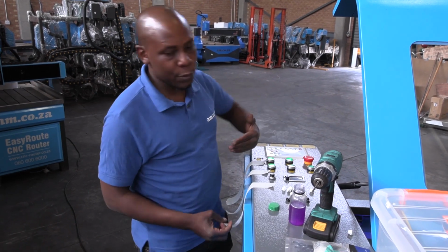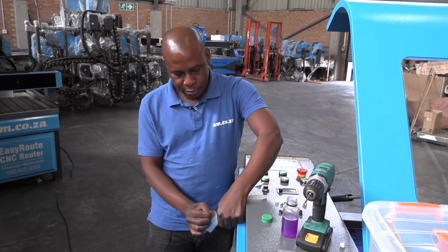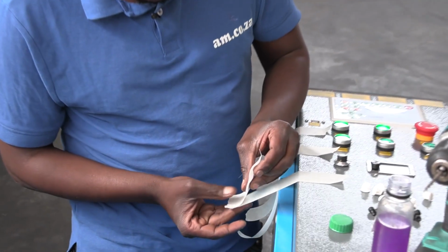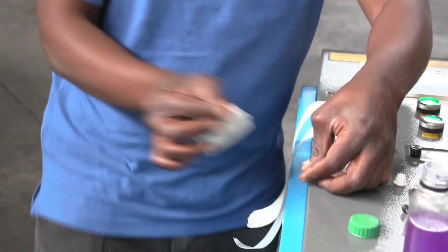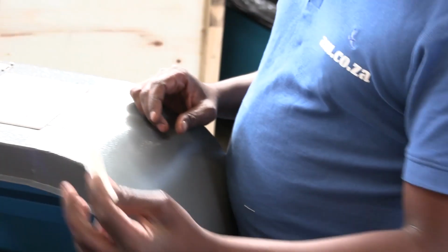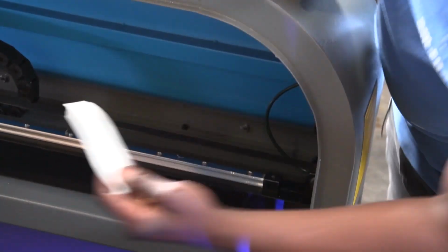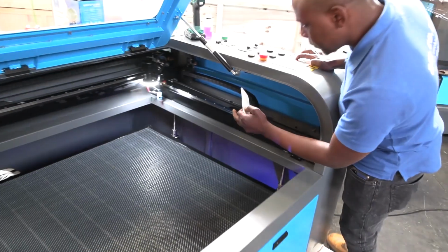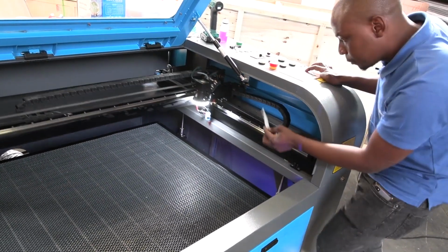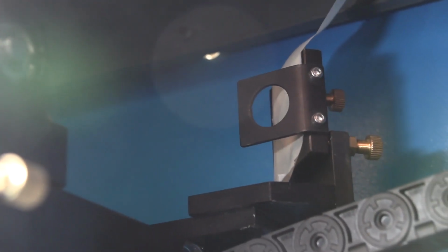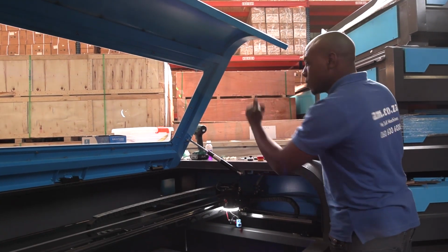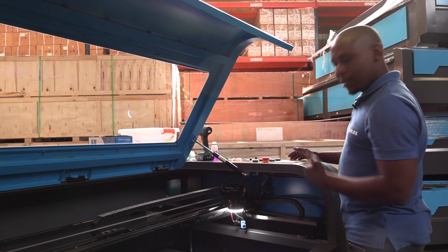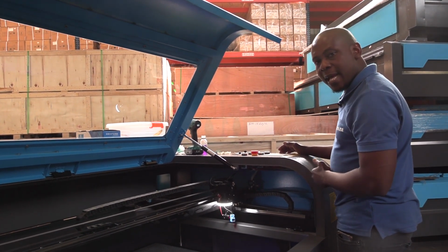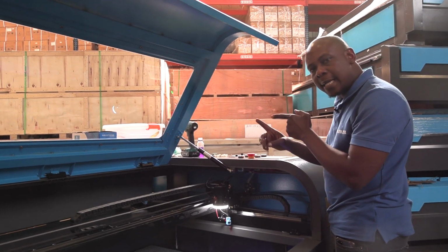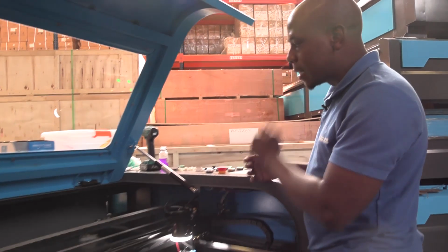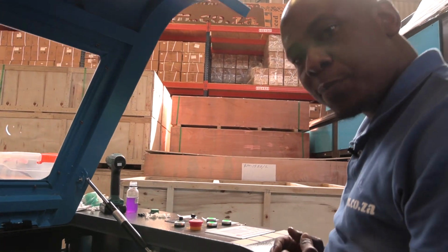Now, I need to align my y-axis. So I'm going to tape over another layer of masking tape and stick this onto the second mirror on the y-axis, which will be the mirror on this one. So what I want to do is pulse it closest to the first mirror, then bring it all the way back, furthest from the first mirror, and pulse and see if it's aligned and hitting the same spot. If not, then I will have to adjust the knobs on the first mirror.